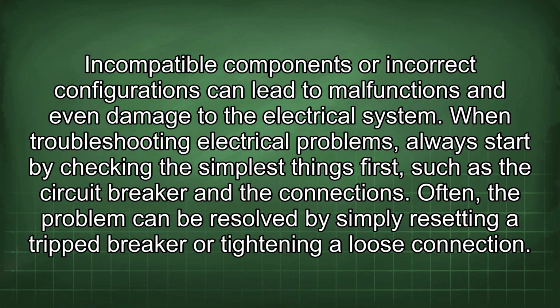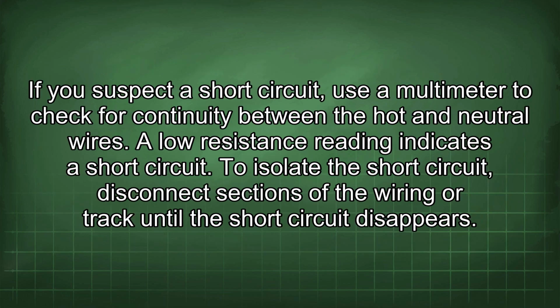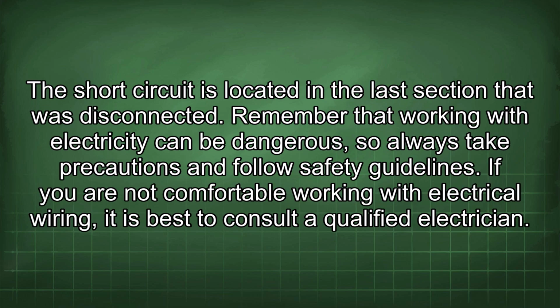When troubleshooting electrical problems, always start by checking the simplest things first, such as the circuit breaker and the connections. Often, the problem can be resolved by simply resetting a tripped breaker or tightening a loose connection. If you suspect a short circuit, use a multimeter to check for continuity between the hot and neutral wires. A low resistance reading indicates a short circuit. To isolate the short circuit, disconnect sections of the wiring or track until the short circuit disappears. The short circuit is located in the last section that was disconnected.